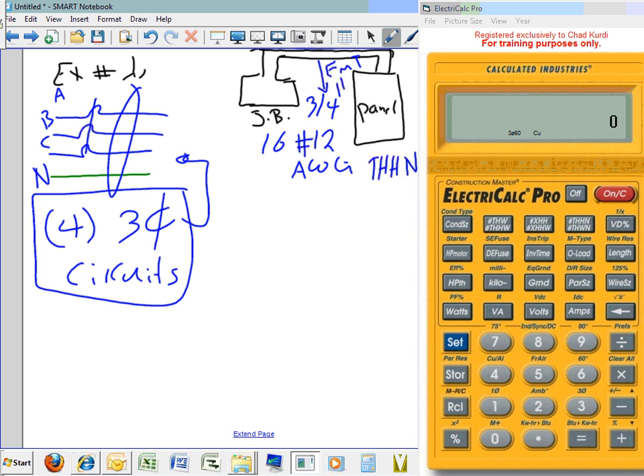And we're putting a 20 amp circuit on each one of them. These are 20 amp single pole circuit breakers tied together with an approved handle, as it should be when you share neutral. All these are multi-wire branch circuits sharing neutral, 3-phase and a neutral, 3-phase and neutral, right? Cool? Okay, what the question is, this is the rating.